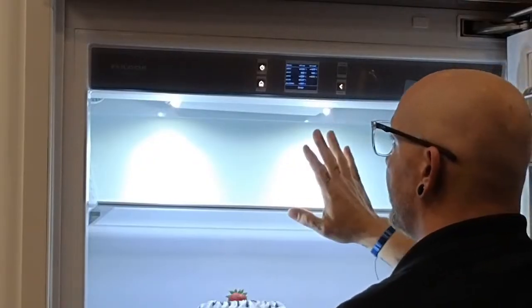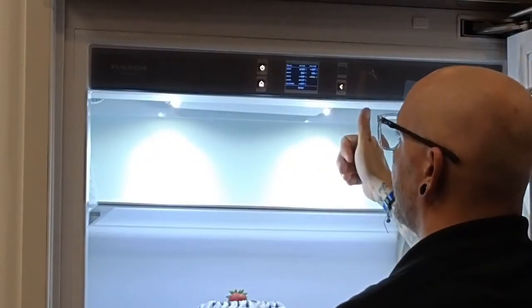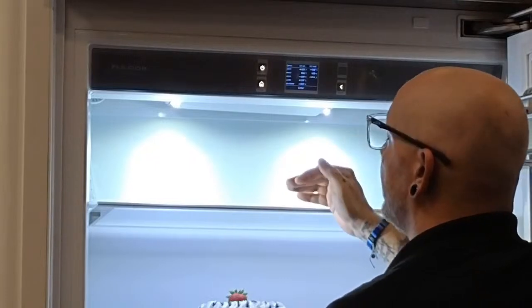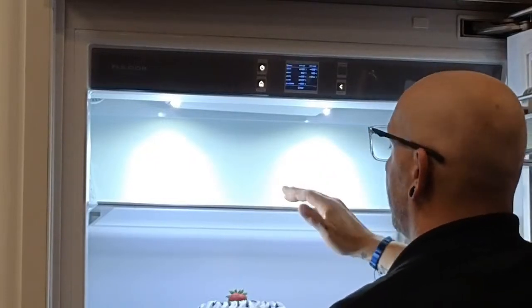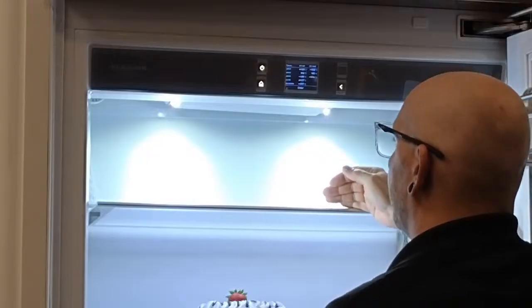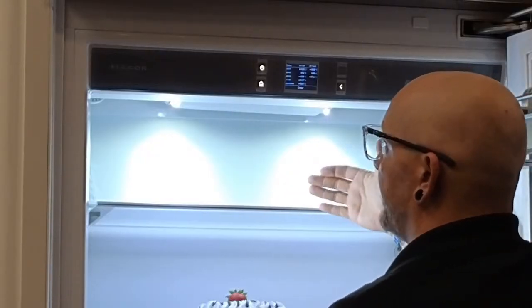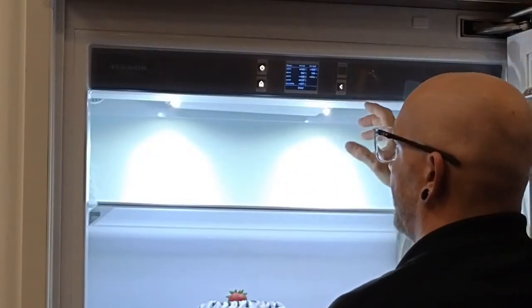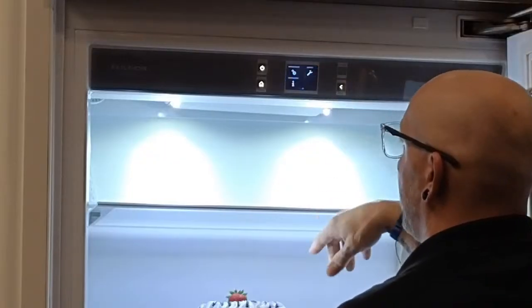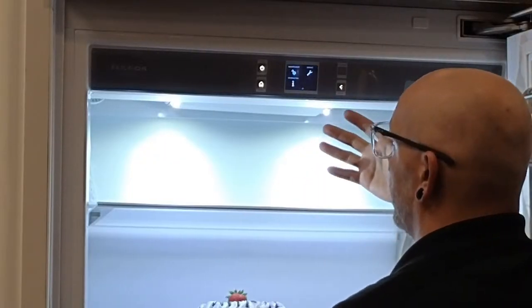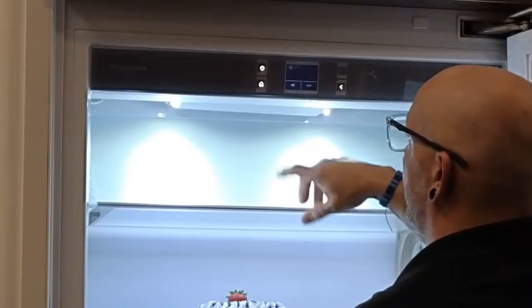If you only wanted to see your sensor readings and you don't want to go into service mode, because once you enter it, you must continue. You can't exit unless you follow the entire program, which is like 32 to 36 steps depending on the machine that you're working on. So as you can see, you can back out of this before going to service mode. So let's actually go into service mode.